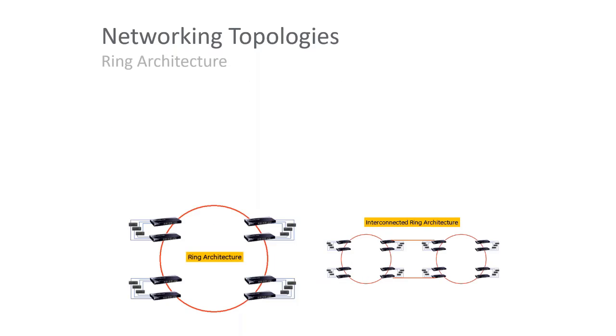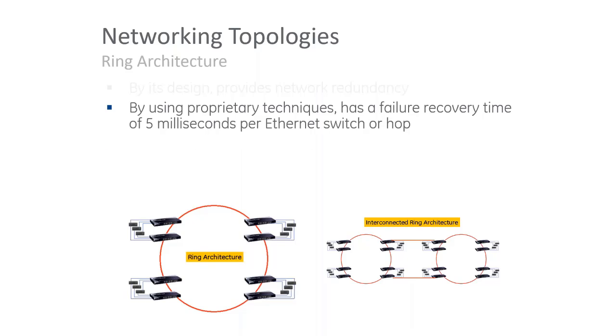The ring architecture is popular in the IT world and provides network redundancy by design. It can use proprietary techniques from manufacturers like Cisco, but there is also the RSTP standard that most switches support to create a ring. If you use the RSTP standard, your switches are compatible with different vendor switches — you're not married to one particular vendor.